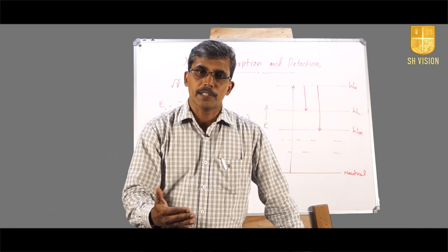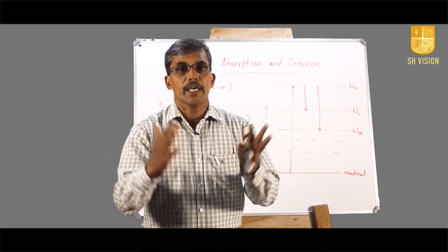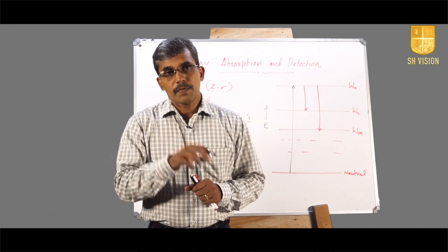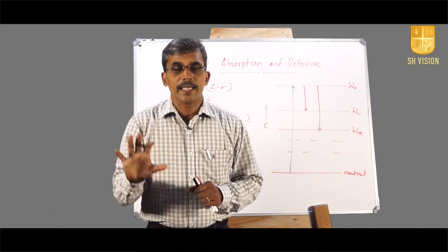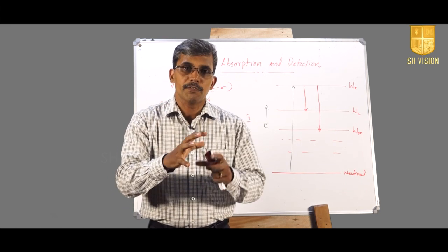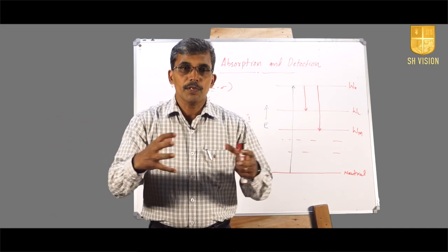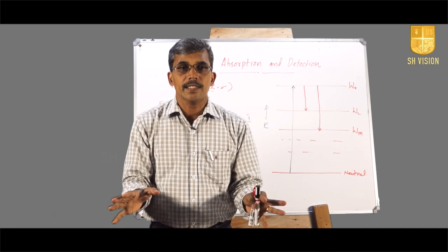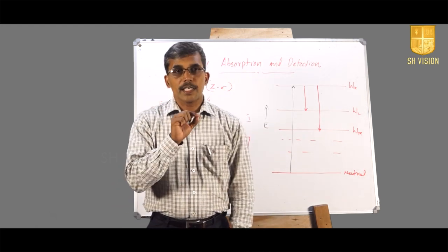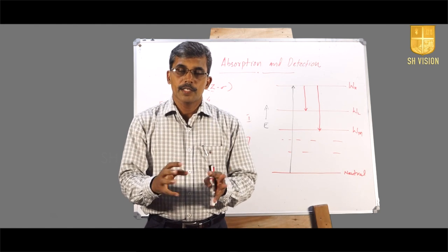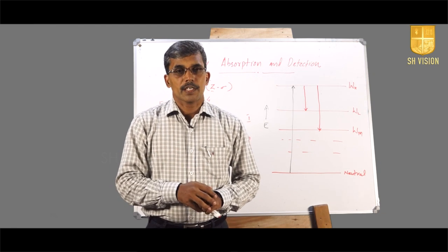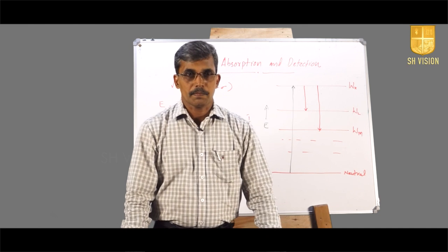So generally a transparent sheet with a photographic emulsion will be given on either side. The thickness of the photographic coating should be high. When this thickness increases, naturally the grain size also increases. In order to get very precise, fine information, we have to enlarge the data. But when we enlarge this, if the grain size has increased, then we will not be able to take perfect information from that film. Therefore, in the case of X-ray, since the grain size is already big, when you enlarge it, the fine information may not be available from the photographic film. This is a difficulty with X-ray photographic film.